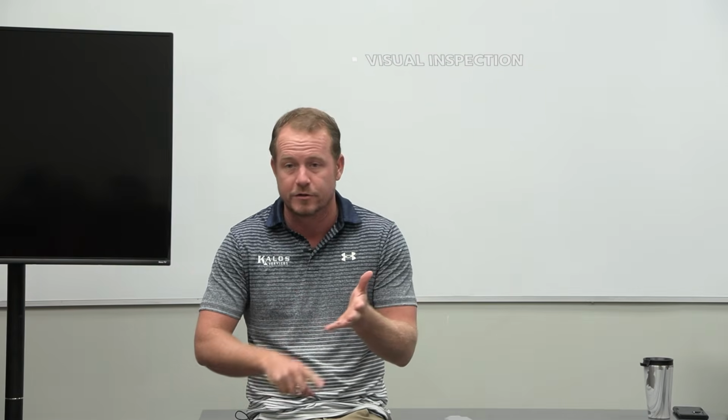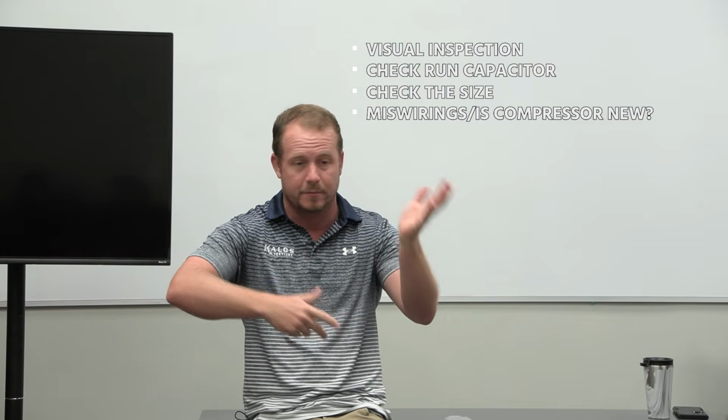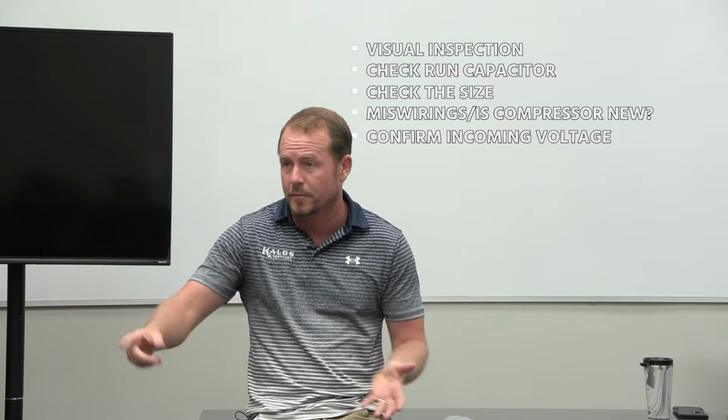So you're going to do visual inspections, you're going to check your run capacitor, you're going to make sure it's the right size, you're going to make sure there's no hanky-panky going on, with somebody miswiring something, putting in a brand new compressor, somebody did something weird here, all that kind of stuff. You're going to want to confirm incoming voltage.